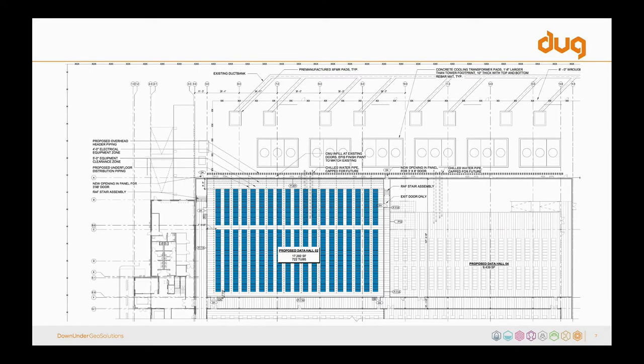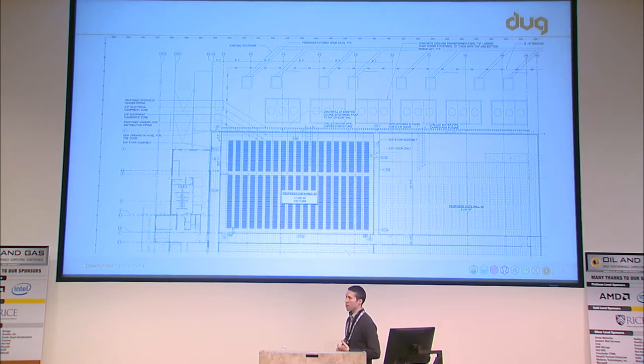We do this primarily through immersion. All of these little blue rectangles are immersion tanks, crammed very close together. We don't need hot aisles and cold aisles to manage airflow, or complex airflow analysis to keep the room cool. Every tank pretty much stands on its own, certainly every row does, which means these aisles and clearways are almost the minimum that code will let us get away with—just enough to get machines and people in and out.